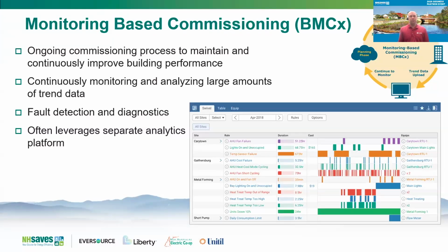Communication is a big deal. You can have a nice, fancy front end with modernized graphics, but if what's behind those graphics is a bunch of old, antiquated, proprietary communications or even pneumatic systems, then you're simply putting lipstick on a pig if you go in and put in monitoring-based commissioning, because you really have to make sure those end devices are working and functioning properly before you can implement monitoring-based commissioning or even retro-commissioning in that case. So you really have to understand what's under the hood of the overall control system. If you do have a modern control system and are interested in monitoring-based commissioning, the takeaway should be that NHSaves is here to support you. We have expertise with the program, so reach out to your utility sponsor for more information.